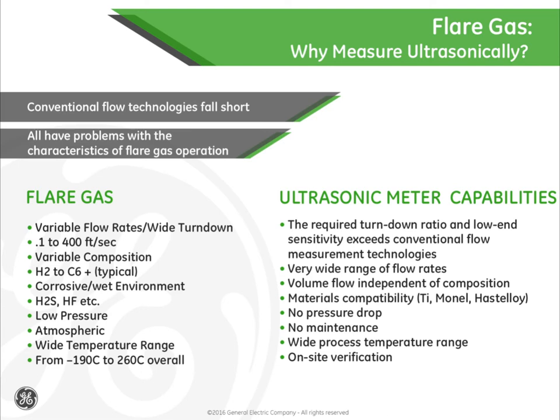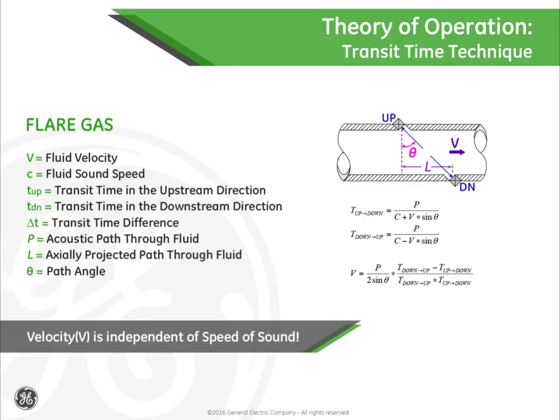The reason why ultrasonic meters operate so well in such a difficult environment is that they have no moving parts that can foul or break. And since they measure flow using ultrasonics, they do not drift or require tuning, ever. The way an ultrasonic meter works is really quite simple. A sound pulse is sent at a known angle with the direction of the flow. The velocity of the sound pulse is increased with increasing flow. The time it takes for the sound pulse to travel with the flow is called the transit time down, or T down. Next, a sound pulse is sent opposite the direction of the flow in the pipe. Since the sound pulse is traveling against the fluid flow, the sound pulse is slowed relative to the fluid flow. This is called transit time up, or T up.